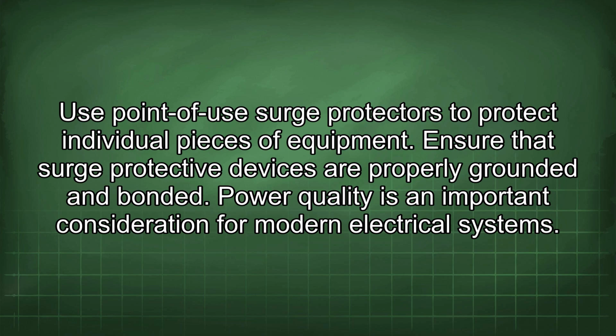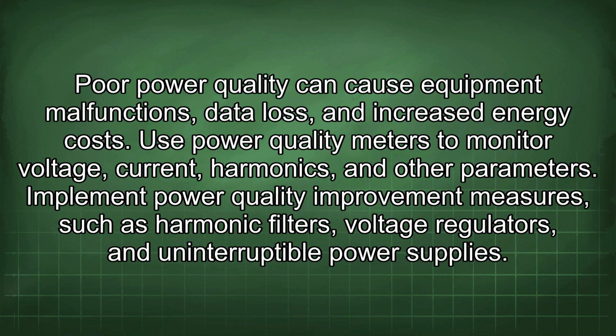Power quality is an important consideration for modern electrical systems. Poor power quality can cause equipment malfunctions, data loss, and increased energy costs. Use power quality meters to monitor voltage, current, harmonics, and other parameters. Implement power quality improvement measures such as harmonic filters, voltage regulators, and uninterruptible power supplies.